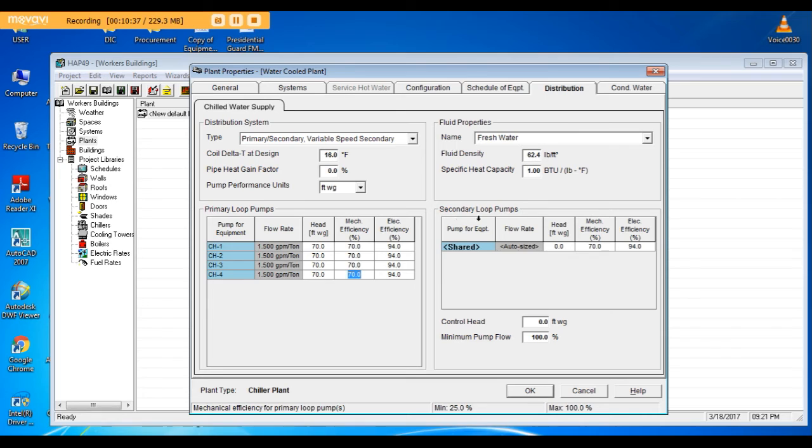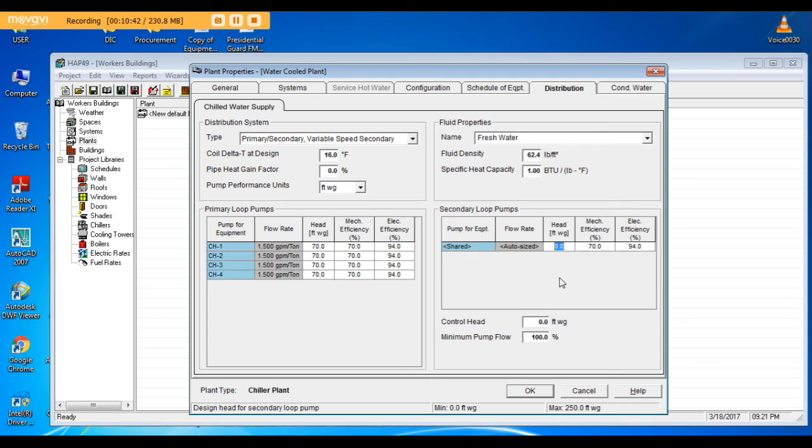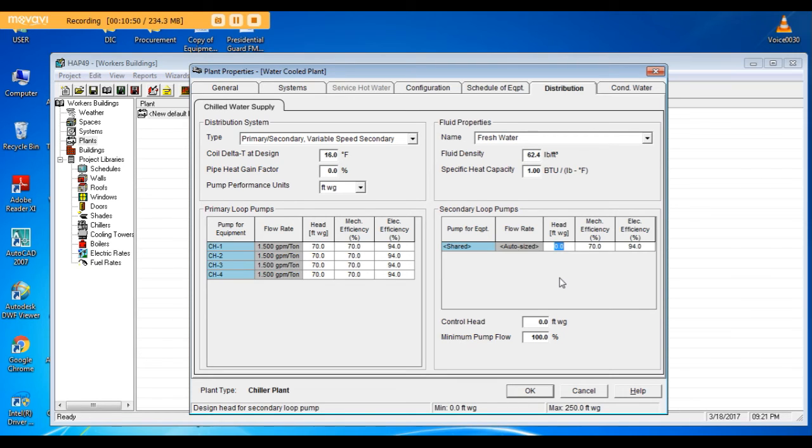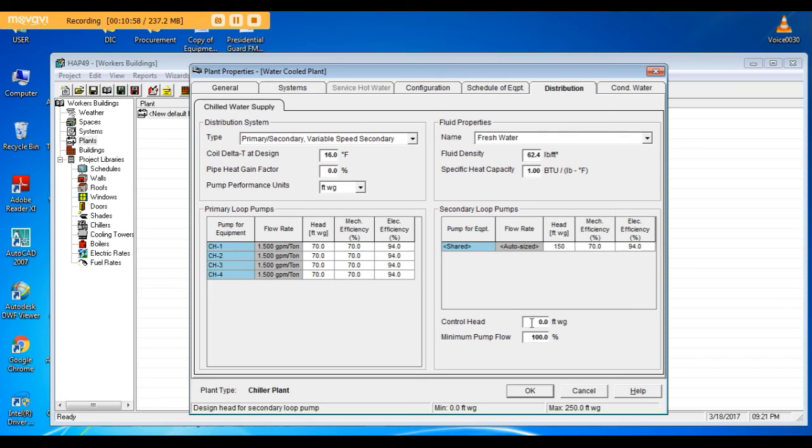Secondary pump, keep it auto sized. Head of the secondary: that is the friction losses in the external network plus buildings or heat exchangers. We have it 150 feet.